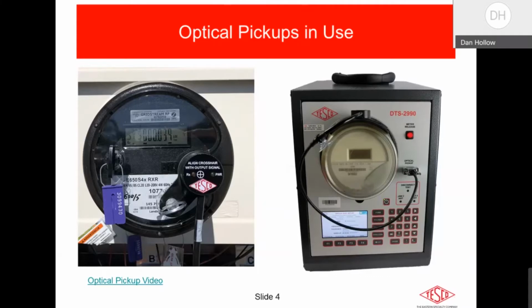So when you're out in the field testing, you're either using the actual customer load, and this pickup is on there and it's counting these pulses, or you're using a phantom load for a service that may not be active at the time, like an irrigation type load or a seasonal type load of some sort, a recreational vehicle park or something that tends to be a seasonal thing. Over on the right is a shop test board, and it has an optical pickup on the top. The optical pickups can be put in whatever position they need to be able to count those infrared pulses and calculate the energy the meter is seeing and reference that back to an internal reference standard in the test device, whether that be a field test device on the left or a shop test device.